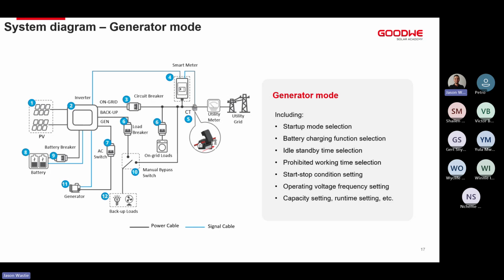If we don't have a generator that's got start-stop functionality like that, we need to use a manual generator, which is what we see more often in a residential space. We can start the generator up on our app. We can just tell the inverter that we have started it manually, and it will open the generator port and allow the generator to continue to operate and provide power to our loads. We'll also set things in the generator configuration settings, like start-stop conditional settings, which are when we want the generator to start up or stop based on battery SOC. Start up when my batteries reach 30%, turn off when my batteries reach 60%, for example, or whatever else we would want to configure.